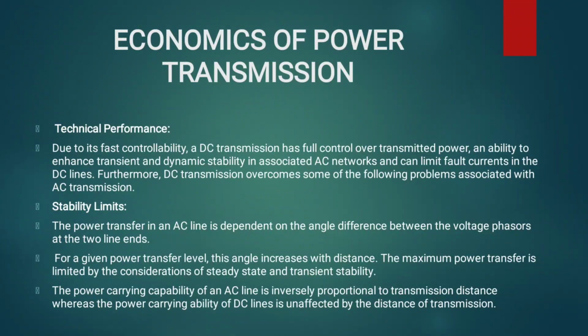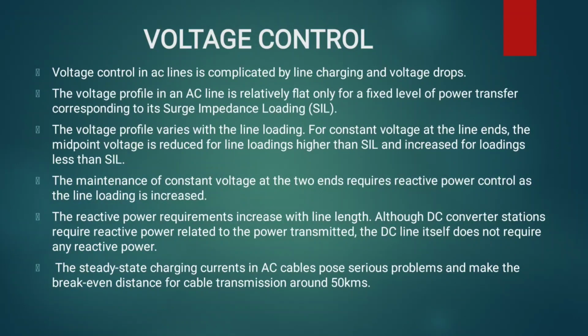Stability limit. The power transfer in an AC line depends on the angle difference between voltage phasors at the two line ends. For a given power transfer level, the angle increases with the distance. The maximum power transfer is limited by the consideration of steady state and transient stability. The power carrying capability of an AC line is inversely proportional to the transmission distance, whereas the power carrying ability of a DC line is unaffected by the distance of transmission.